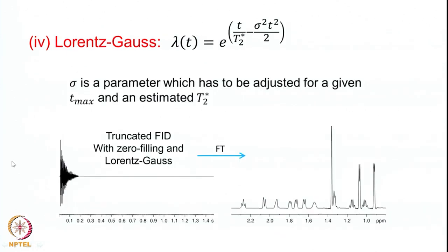One more function is the Lorentz-Gauss function: e^(t over T2_star minus sigma squared t squared over 2), where sigma is a parameter adjusted for a given T_max and estimated T2_star. Multiplying the FID by this function gives a smoother FID going to zero, with reasonably good signal-to-noise and digital resolution after Fourier transformation. Combining zero filling and multiplication by suitable functions, you can get better signal-to-noise ratio as well as better resolution. These are the cosmetics of data collection and processing, and one must optimize these parameters for better signal-to-noise ratio and better resolution in your spectrum.